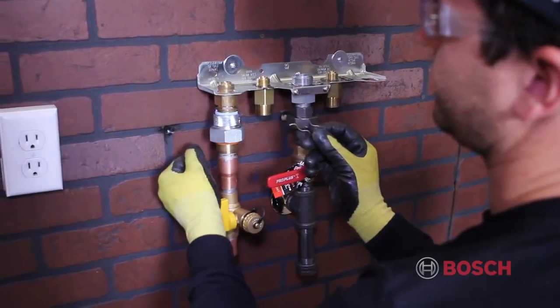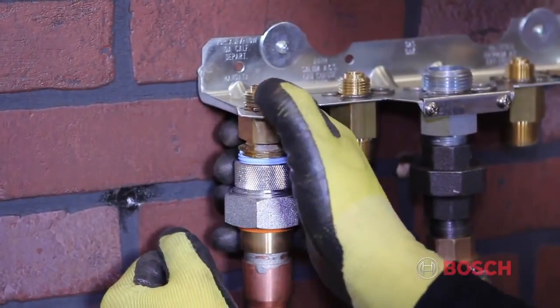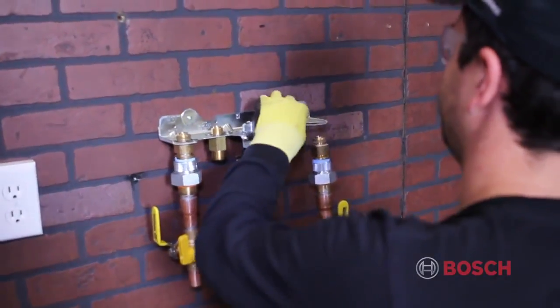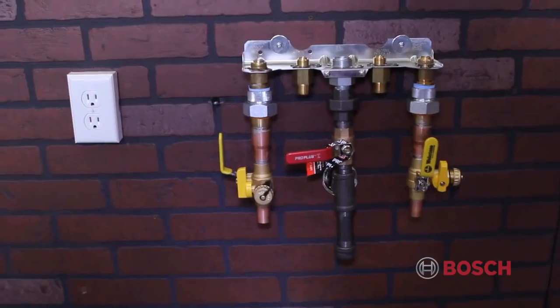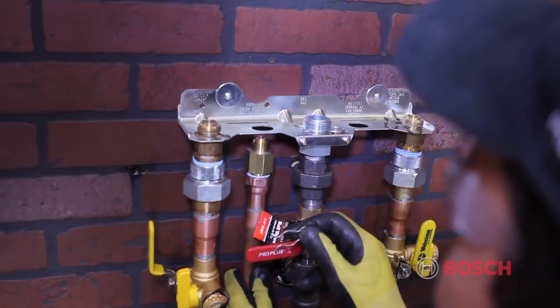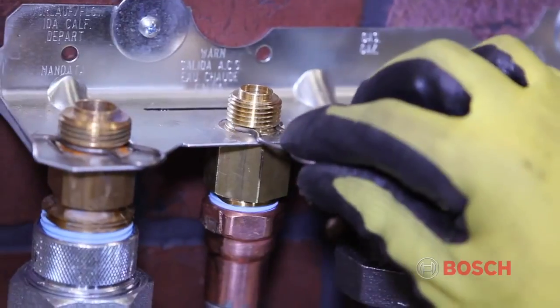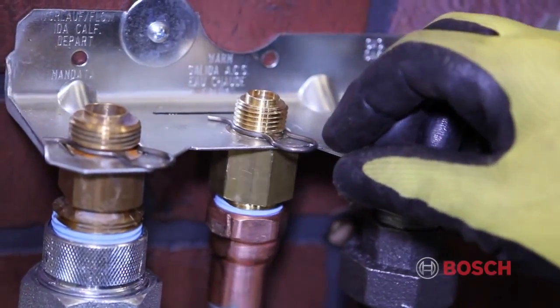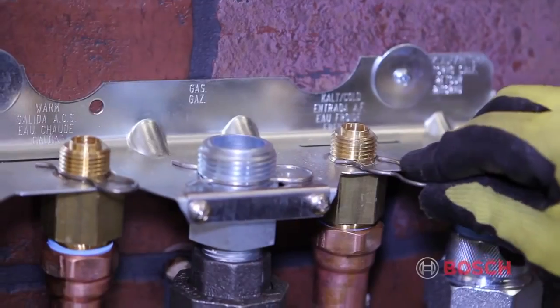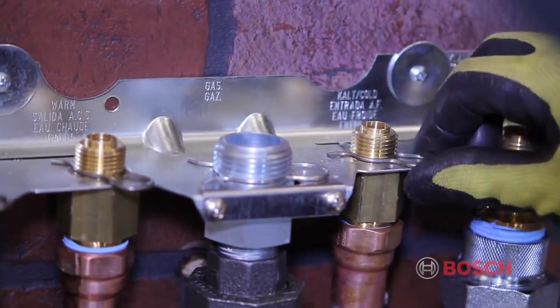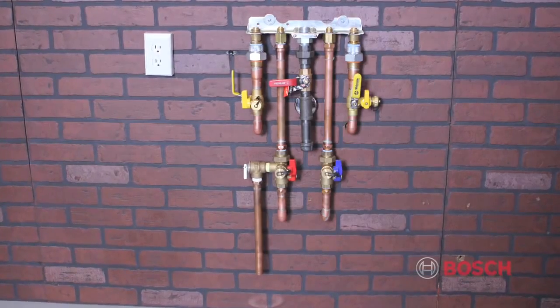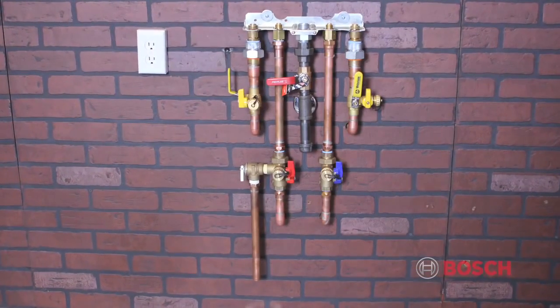The installation of service valves in the supply and return connection is recommended. These valves are important for proper system commissioning and future service calls. The domestic cold water in and hot water out are 3/4 inch male connections. The flat plate heat exchanger located inside the combi boiler may require descaling down the road, so we recommend installing service valves on the hot and cold side of the boiler.